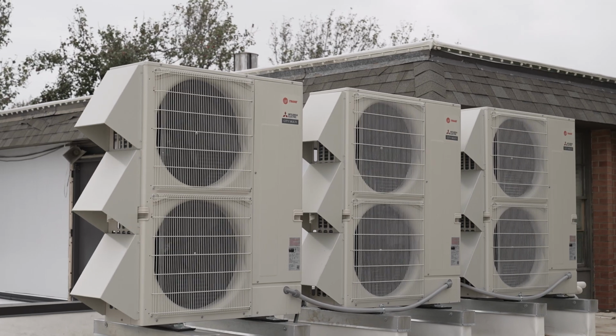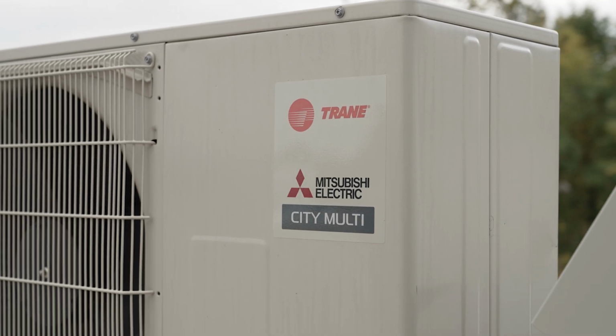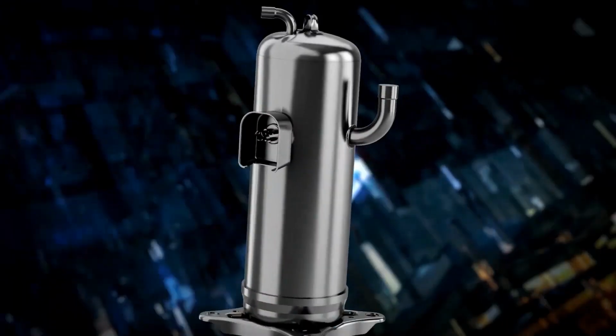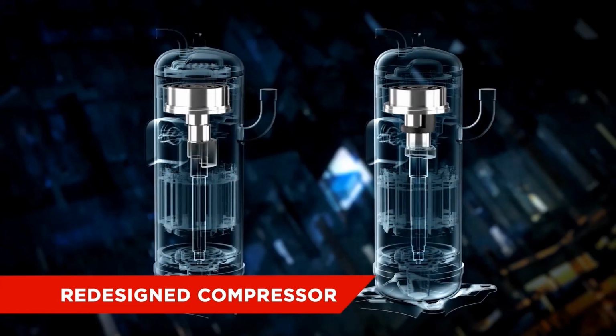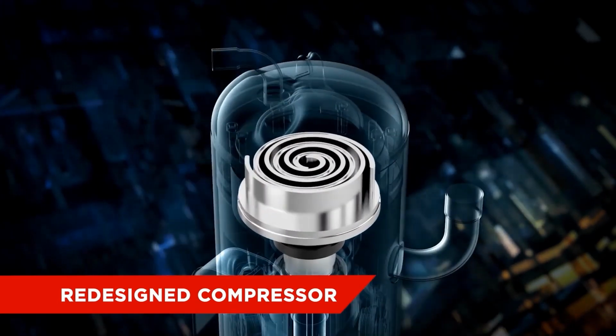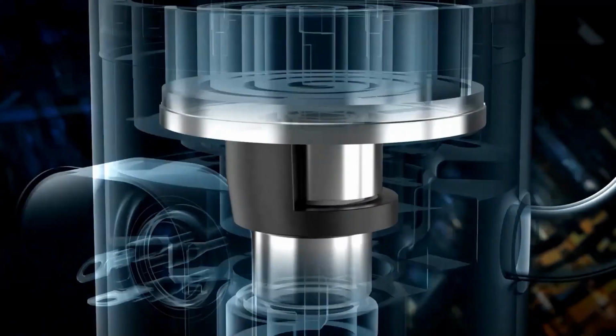The great thing about the City Multi VRF systems is it has an inverter-driven compressor. The variable refrigerant flow heat recovery system allows us, via refrigerant, to extract the heat from the zones that are calling for cooling. You take that heat, remove it, transfer it via the refrigerant to the zones that may be calling for heating, and it rejects the heat in those heating zones. That allows us to be truly efficient, utilizing just enough energy to answer the demand of the systems while also providing comfort cooling.